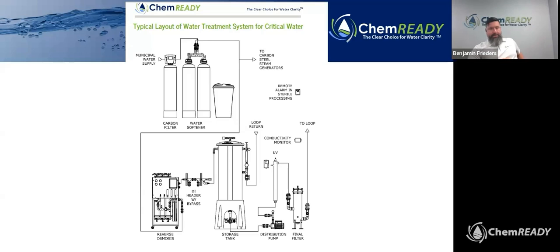And then, if that wasn't enough, you also have to have some additional filtration and disinfection, typically including UV and a final bacteria and endotoxin filter. All of that will feed to, now a requirement, a recirculation loop that would feed your washer disinfectors, steam sterilizers, and any other equipment that requires your critical water. Once those are fed to those devices, you would then have a return loop that comes back to the storage tank and then continuously recirculate that into a loop. So right off the bat, if you know you don't have most of these pieces of equipment, you can be pretty sure that you're not in compliance, and you're probably going to need to look into some capital expenditure for this.